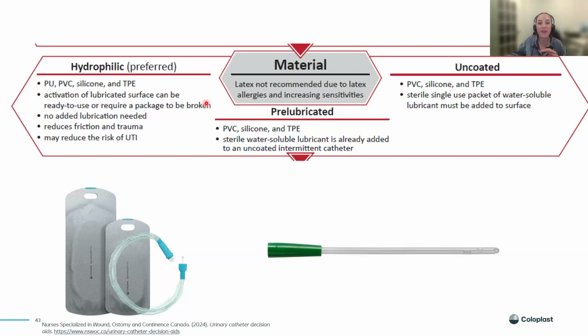Hydrophilics have their hydrophilic coating already embedded onto the surface of the catheter, and that coating becomes activated with a liquid solution. You do not need to add any external lubricant to hydrophilic catheters. This is such an advantage, and it potentially helps to reduce the risk of contamination, because you're not having to add that step for patients. Some patients also complain that adding lubricant can be messy, so this can make things a lot easier, cleaner, and more hygienic for them.